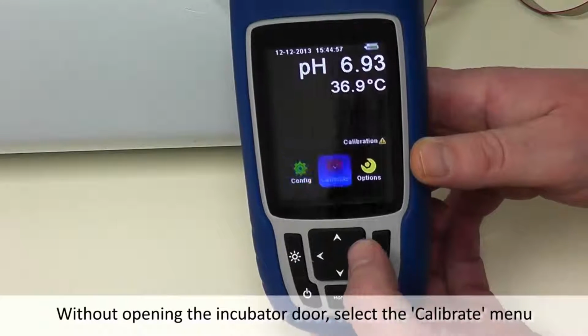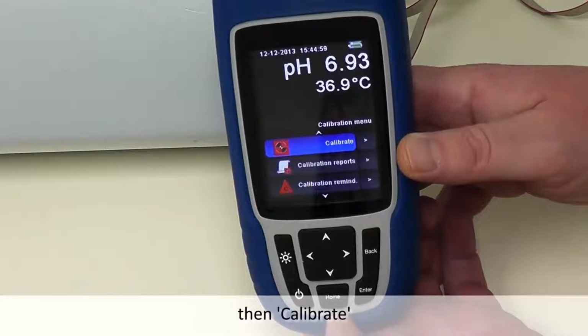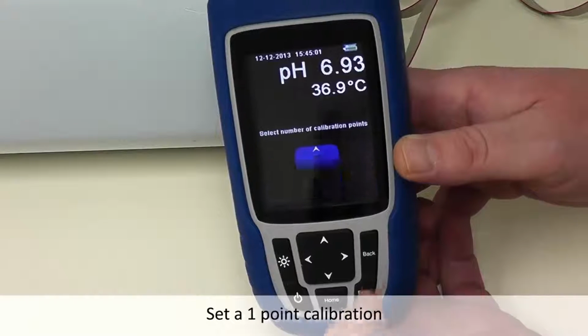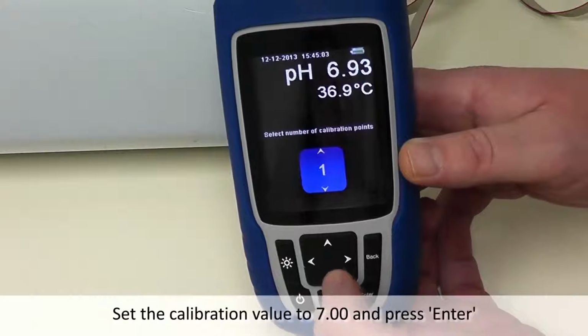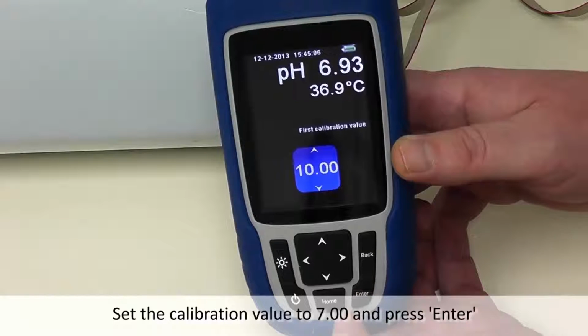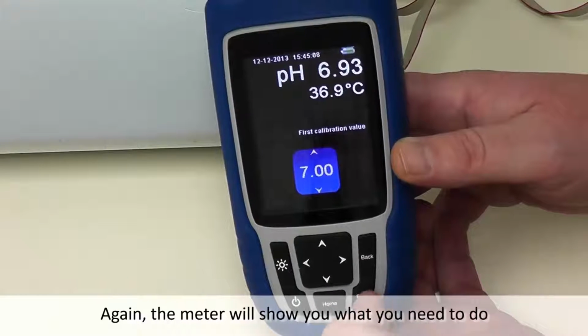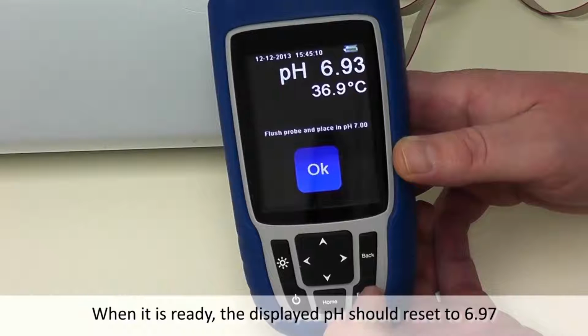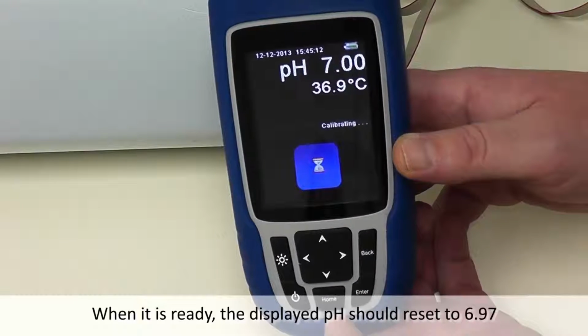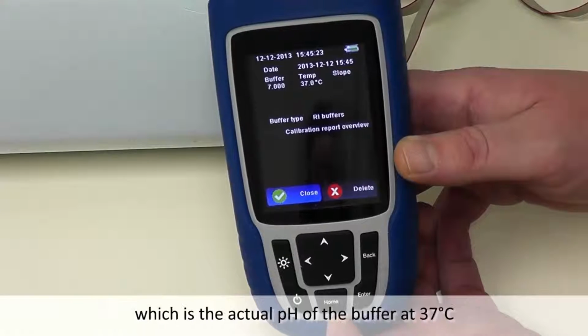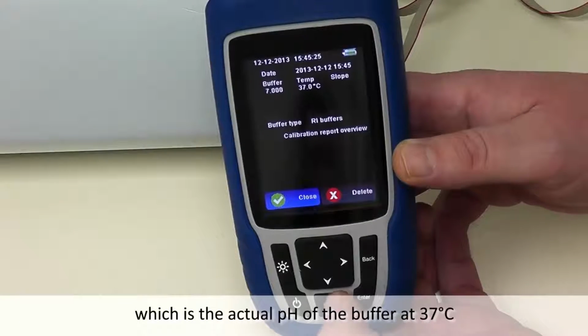Without opening the incubator door, select the Calibrate menu, then Calibrate. Set a 1-point calibration. Set the calibration value to 7 and press Enter. Again, the meter will show you what you need to do. When it is ready, the displayed pH should reset to 6.97, which is the actual pH of the buffer at 37 degrees centigrade.